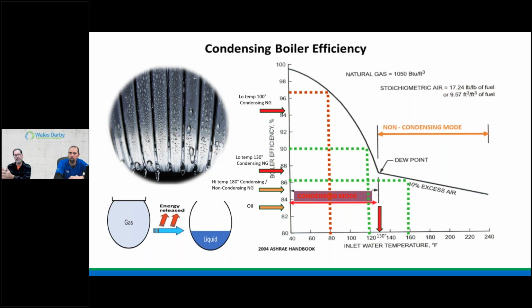Remember, we deliver BTUs, not heat, not temperature, right? Temperature determines our emitter's output, and that's where we might have to play with why certain areas or certain temperatures are needed. But I don't think it's so much the temperature everybody's afraid of. I think it's the work needed to do the heat loss to make sure that we are providing the right amount of BTUs to the space. Because you do the load calc, you do a heat loss and a Manual J, and the numbers don't lie. So and there's fudge in there. Exactly. And there is extra. There is the pad there. You know what I mean?